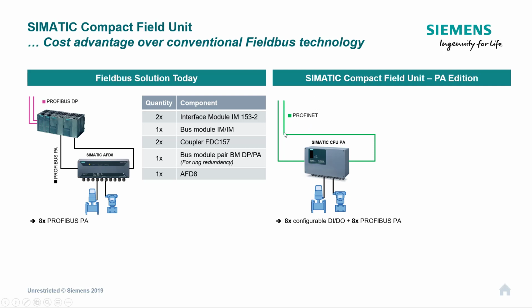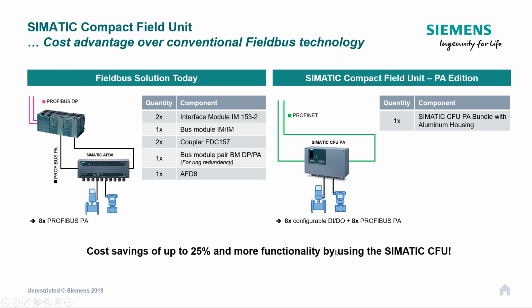I don't need a cabinet, I can come straight from my PLC or my automation station into this and wire it as a redundant ring, and then I have my 120 meter spurs off to each instrument. So if we have a look at the bundle, there's a compact field unit Profibus PA bundle, aluminium housing, so you get everything you need in one housing, and that can be a cost saving of up to 25% compared to your conventional method of installing it.